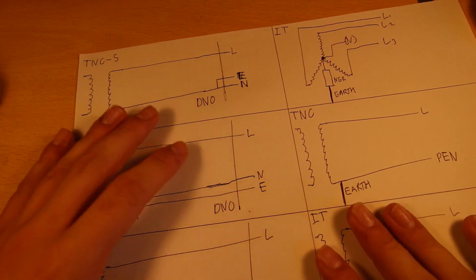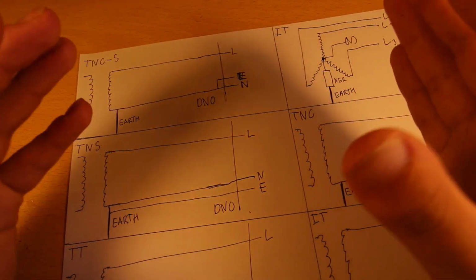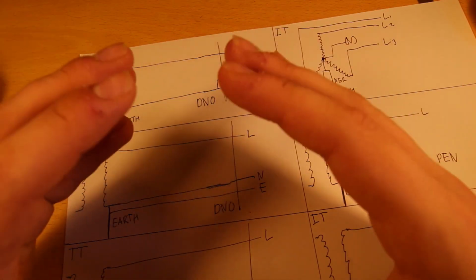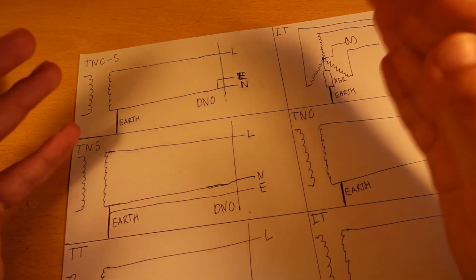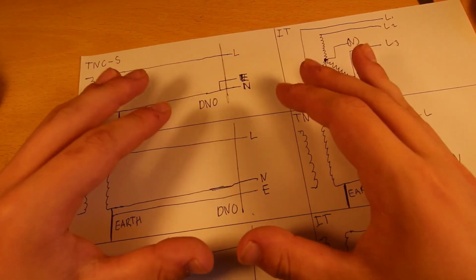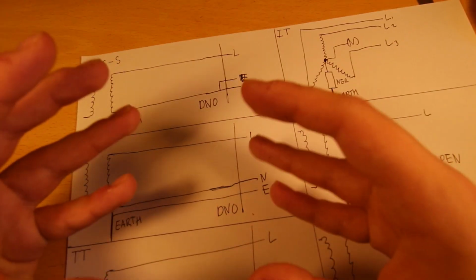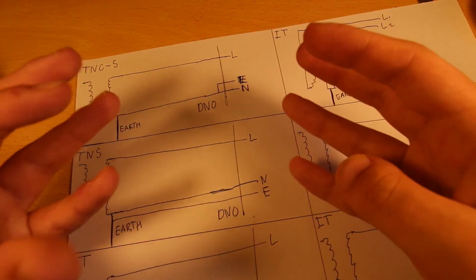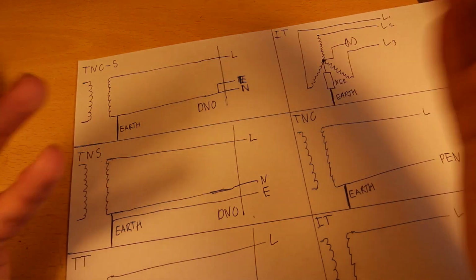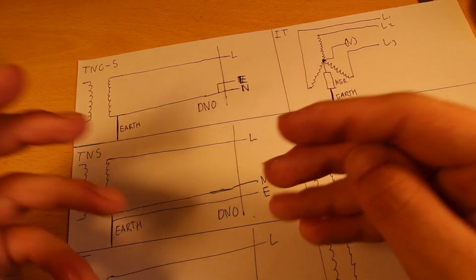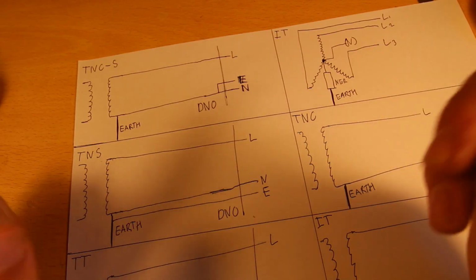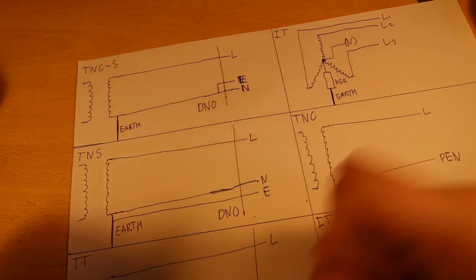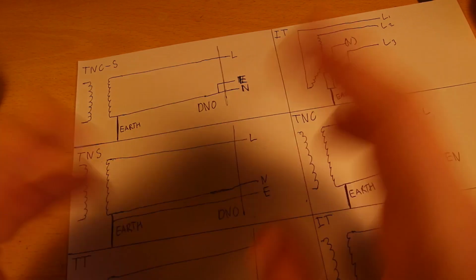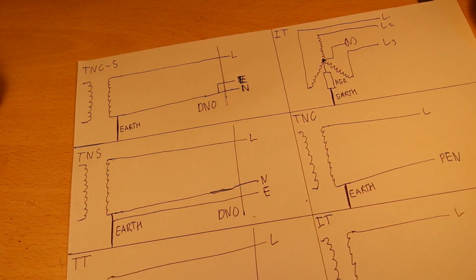The issue I was going to get into now is the problem of PEN faults, and how PEN faults can be really, really dangerous, because it can result in all of the earth metalwork in the installation basically becoming live. And they can also result in fires because of a phenomenon known as a diverted neutral current. I will get another diagram now to try and explain how a diverted neutral current works.